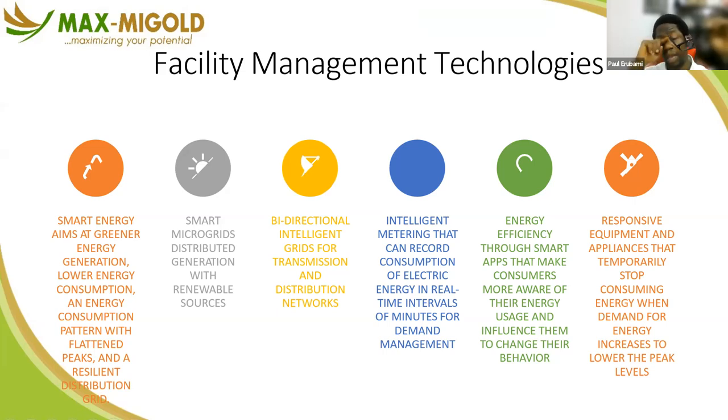And so instead of getting a 250 kVA generator, for example, I can use a series of 20 kVAs and solar panels that can pull in about 300 kilowatts or 200 kilowatts of energy from sunlight on a very bright day, right? So what that means is I'm actually providing capacity for my off-peak load using the generators. And they don't even have to all kick in at the same time, right? With a synchronizing panel, they can kick in one by one by one, and my energy consumption will automatically be squeezed to the barest minimum, right?